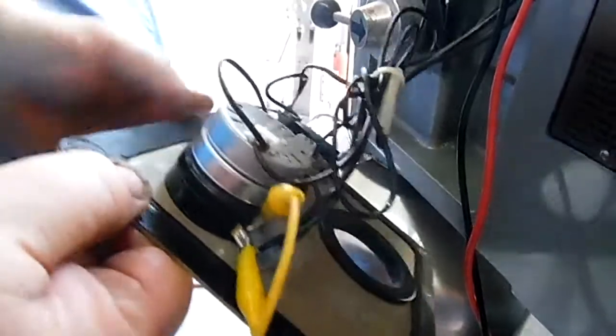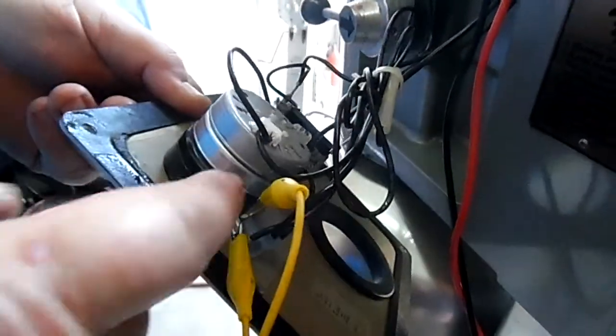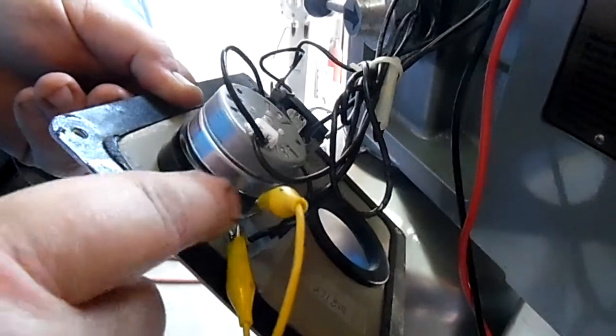The timer is an electromagnetic timer. One and two is your switch area, three is power for the timer. You really only need to be concerned with one and two. If you think the timer's bad, you can actually jump it like I did in this case.